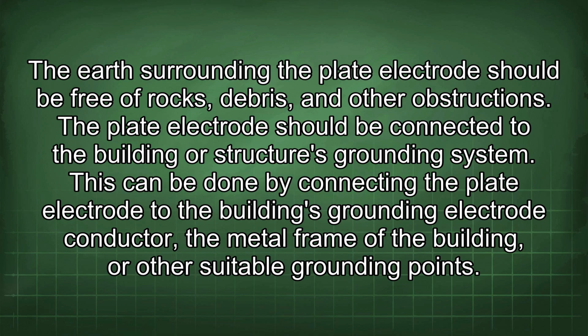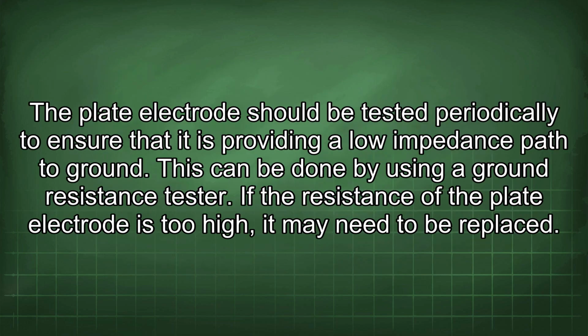The plate electrode should be connected to the building or structure's grounding system. This can be done by connecting the plate electrode to the building's grounding electrode conductor, the metal frame of the building, or other suitable grounding points. The plate electrode should be tested periodically to ensure that it is providing a low impedance path to ground. This can be done by using a ground resistance tester. If the resistance of the plate electrode is too high, it may need to be replaced.